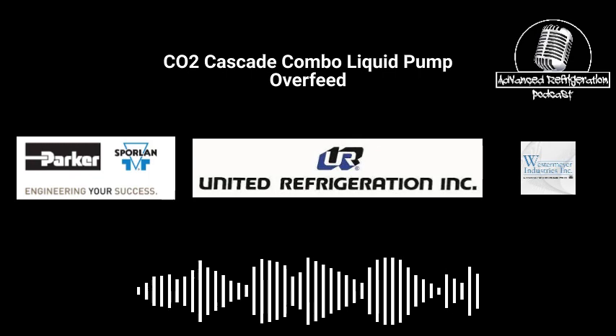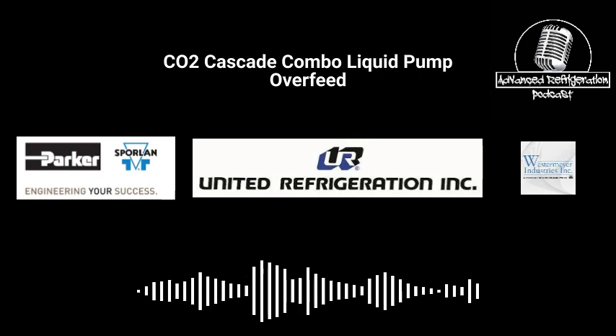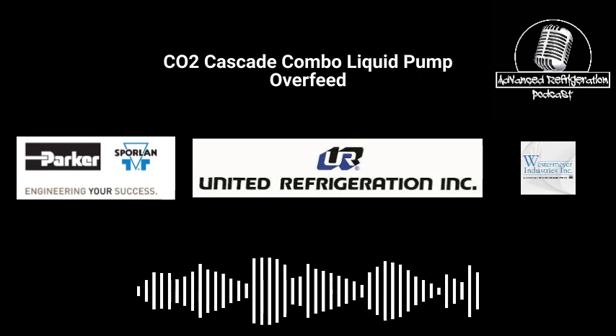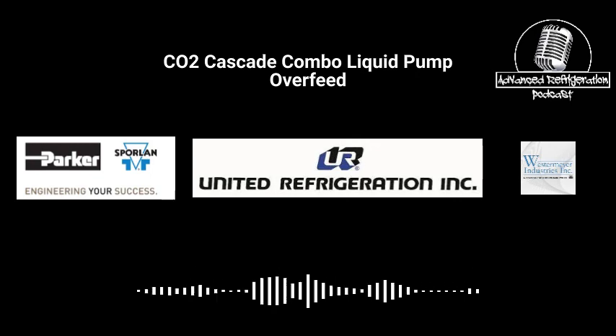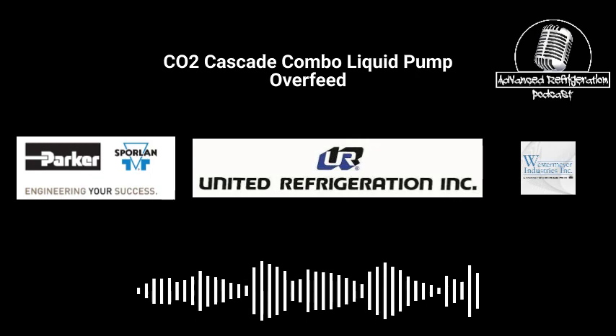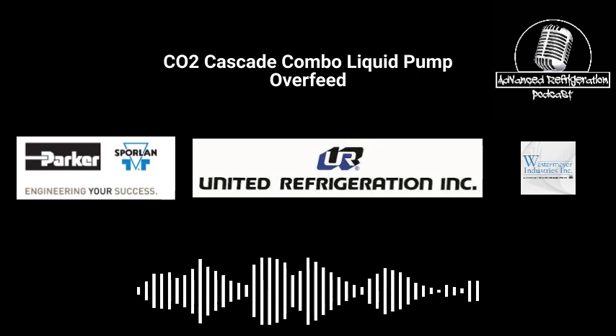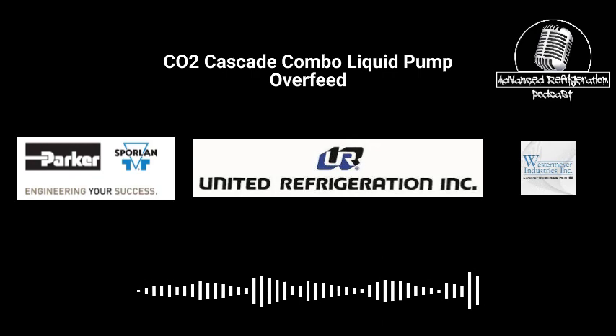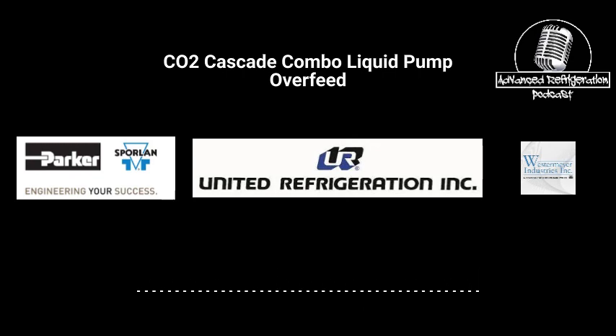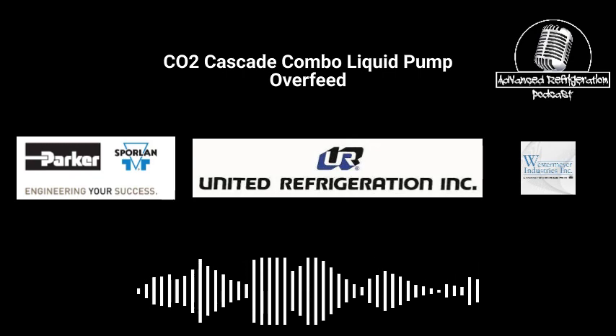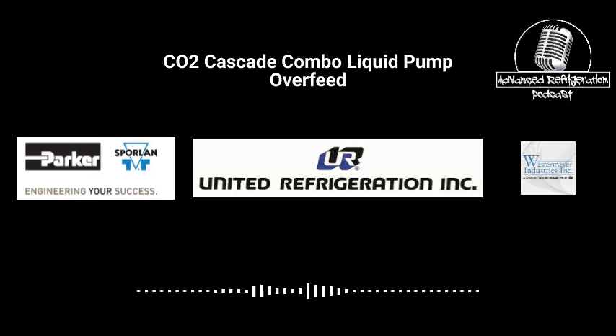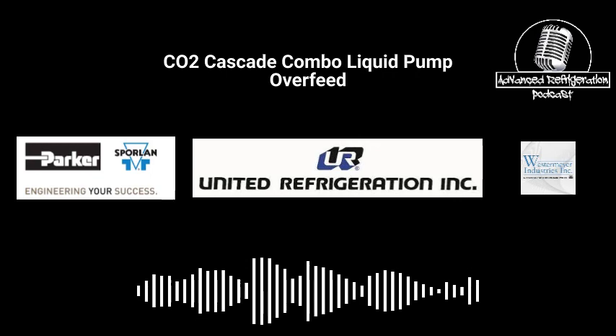Whatever it is, it's whatever you're trying to maintain that medium fluid at. So say if it's 18 degrees, we'll say it's 425, for example. You're pumping that liquid CO2 at 425 pounds through the store. It's pumping through the store, cooling the cases, and then it's coming back and dumping back into the receiver.